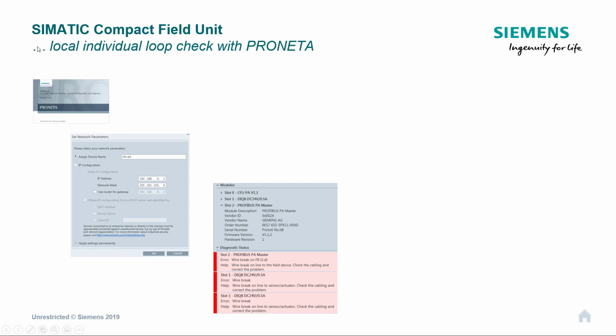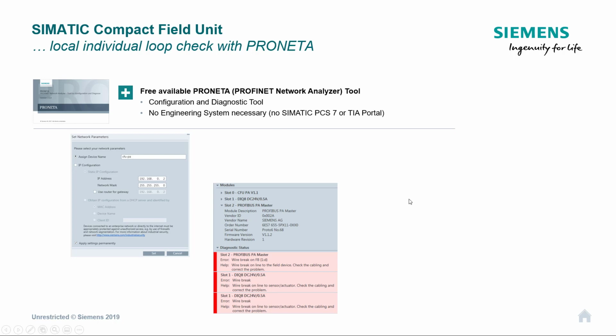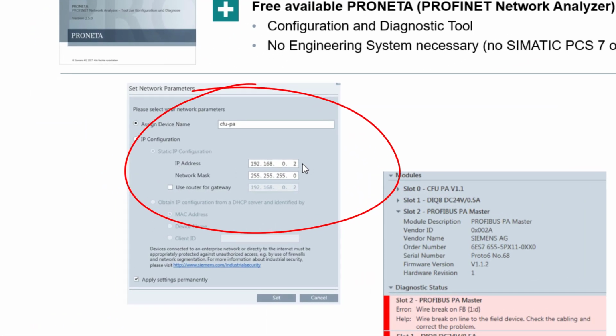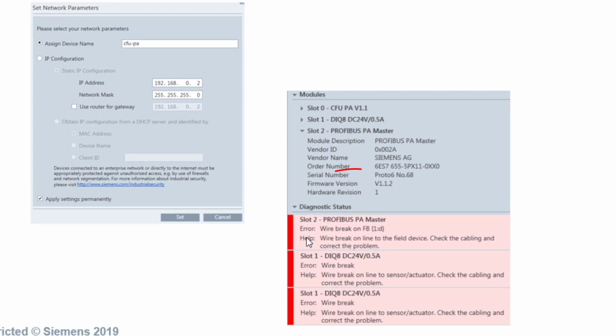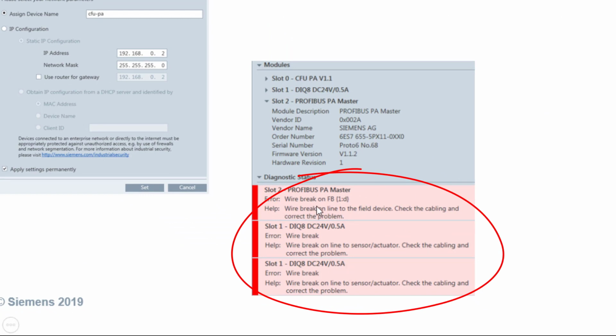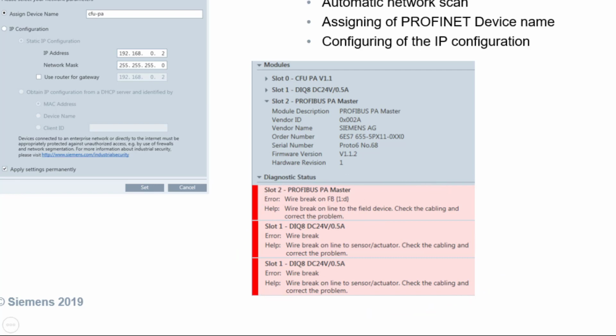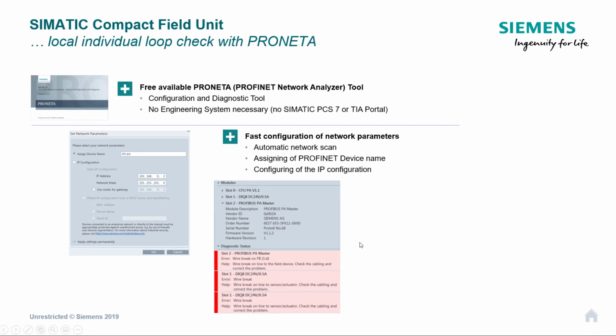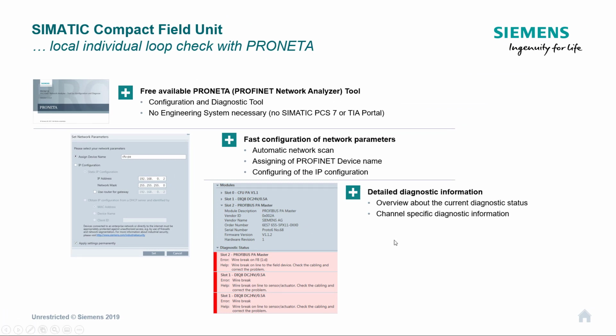This I only recently found out about. I've known about PRONETA for a while, but I normally use it for scanning a network to tell me what's on there, and then as you can see here, I can change the IP address, but more importantly with Profinet we need to be able to assign the name. That's unique to Profinet, this name, so when it connects to the PLC it's not just looking at the IP address, it's looking at the device name as well. But the nice thing is it actually brings back the diagnostics of the Compact Field Unit, so you can see here wire break on Profibus PA on FB slot 2.